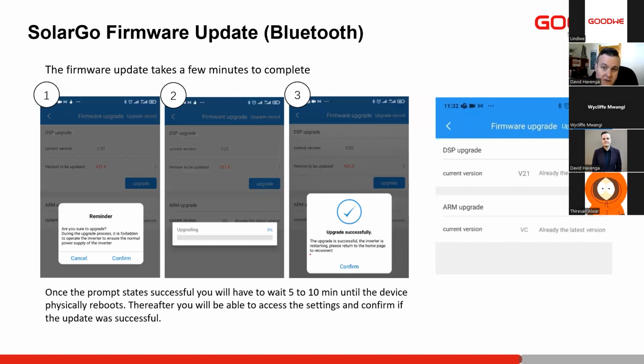The only thing you can do to check it is try and connect to it via the app again. If you can connect to the inverter via the app and you are getting data from the inverter and you can verify the firmware version, then you know it's complete. Never think, maybe it's taking too long, I need to restart it. Never do that, because if it's busy writing the firmware to the flash and you restart it, you can cause the inverter to not have any firmware on it. It's very important to make sure we have a stable power connection and we do not switch it off during this process.